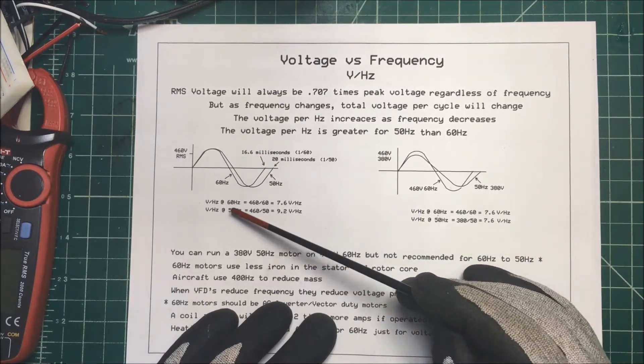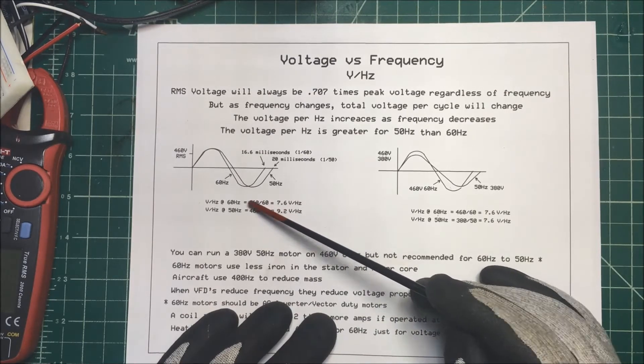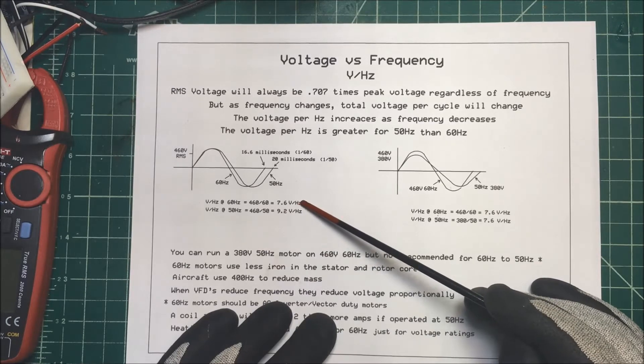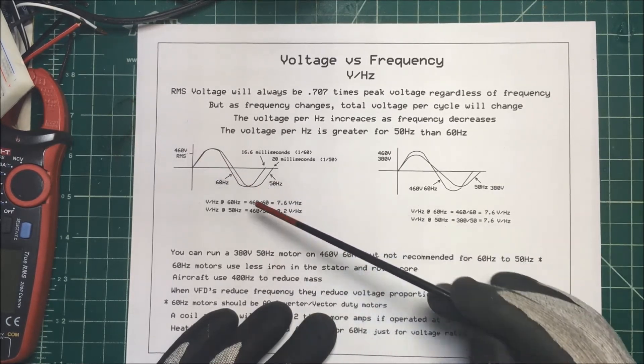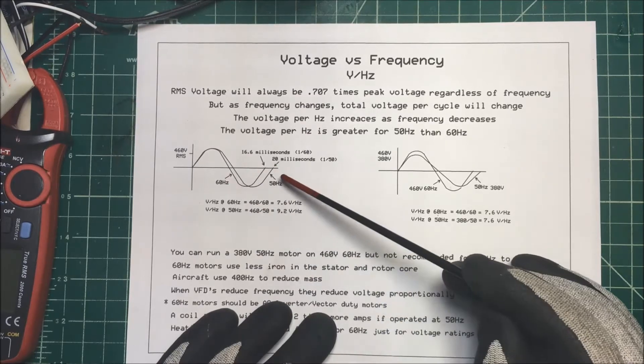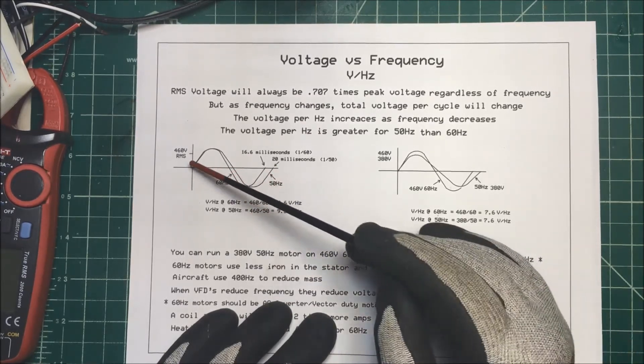So if we calculate the volt hertz for each of these, we take our 60 goes into 460, we get 7.6 volt hertz. And if we take our 50 and we divide that into our 460, we're going to get 9.2 volt hertz. So your voltage is going to be greater for this time period.